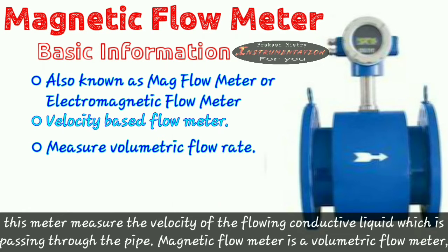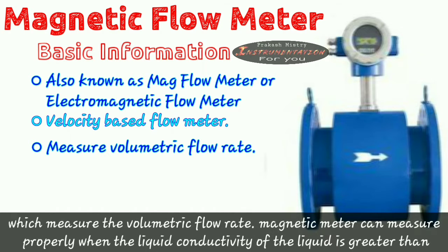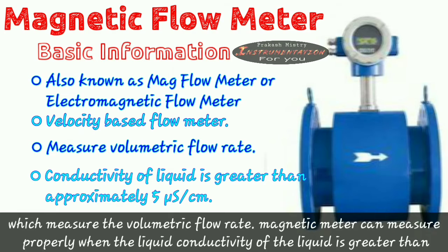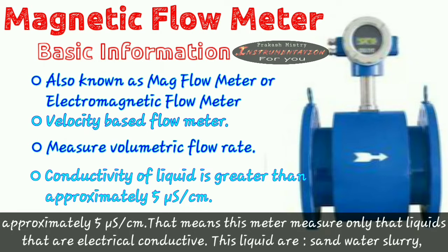Magnetic flow meter is a volumetric flow meter which measures the volumetric flow rate. Magnetic meter can measure properly when the liquid conductivity is greater than approximately 5 microsiemens per centimeter. That means this meter measures only that liquid that are electrically conductive.